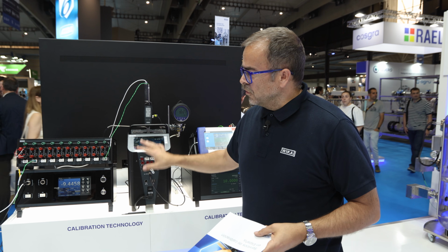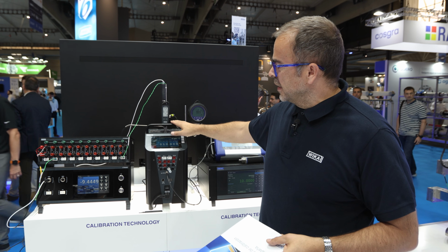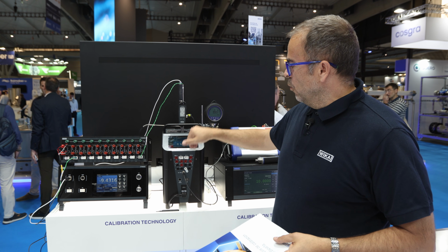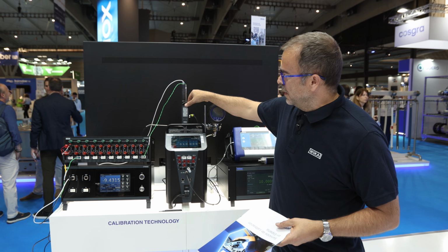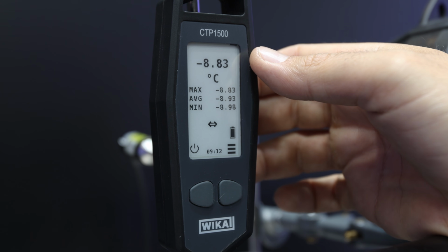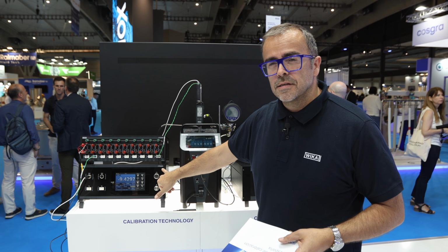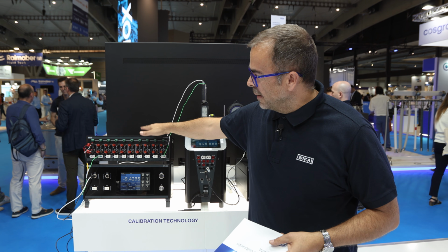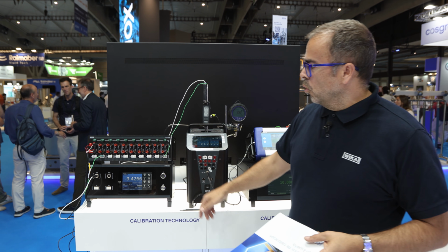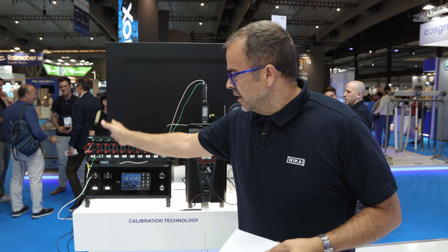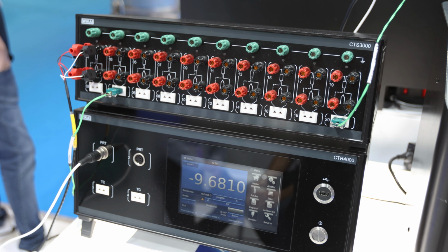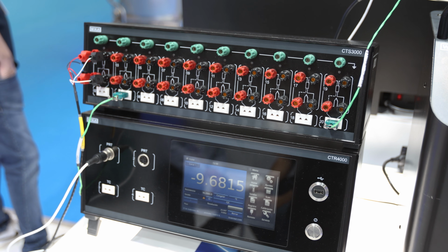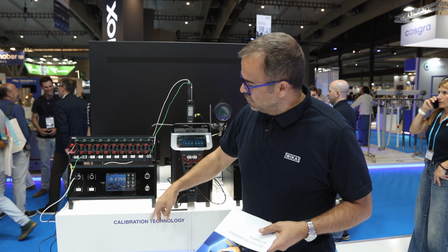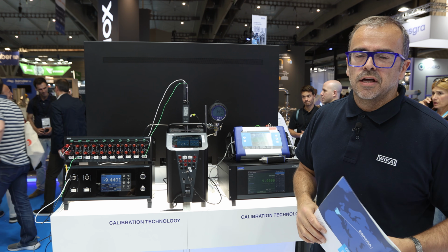Now for the temperature section, we have a dry block multifunction down to minus 10. This could be the device under test, and we have a temperature reference, the CTR 4000 plus multiplexer. The good point is you can see different channels here, and control up to 10 channels at once with the CTS 3000.